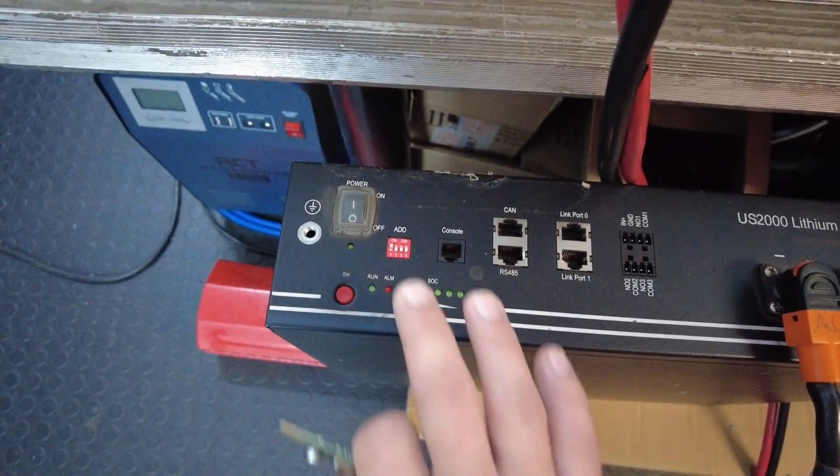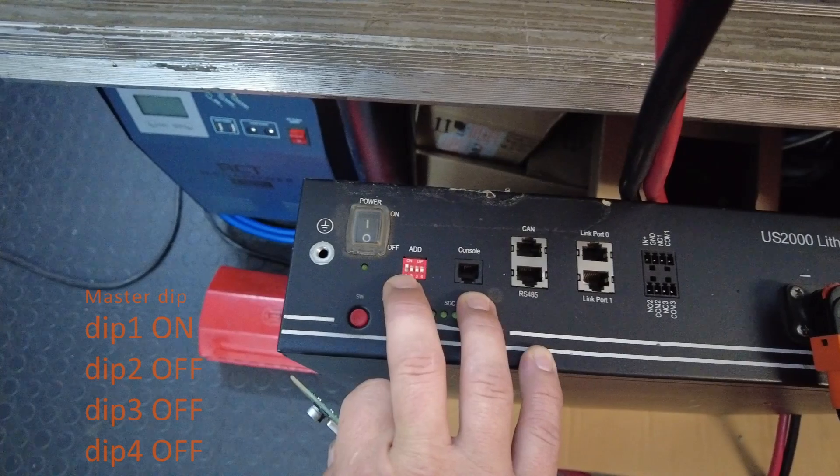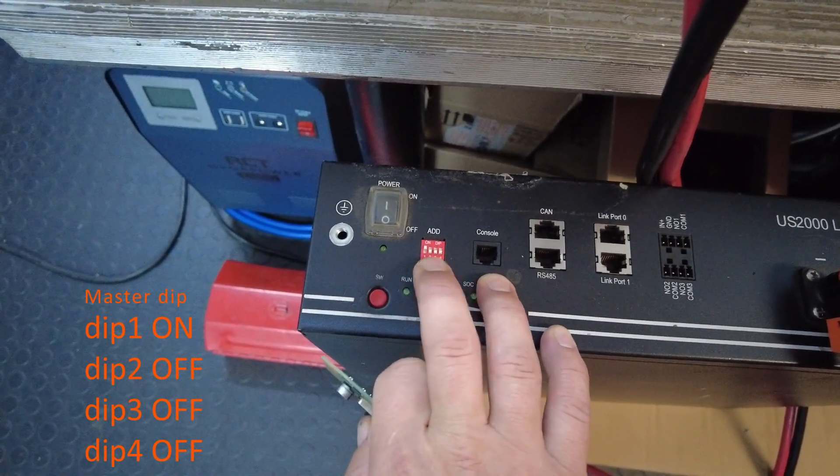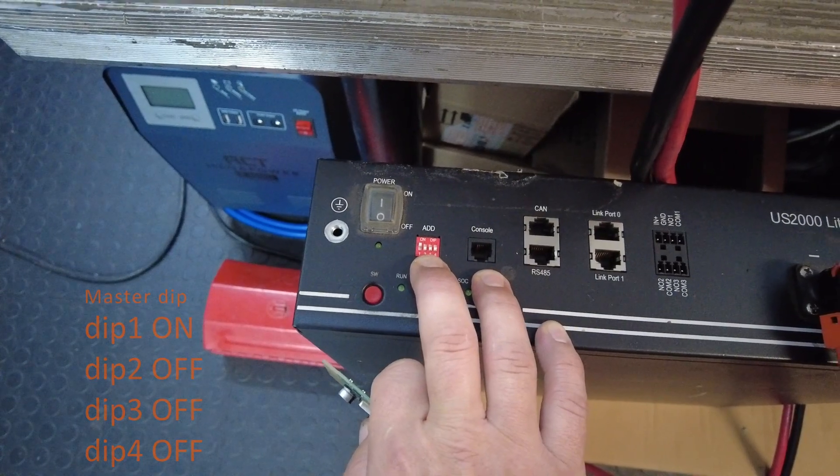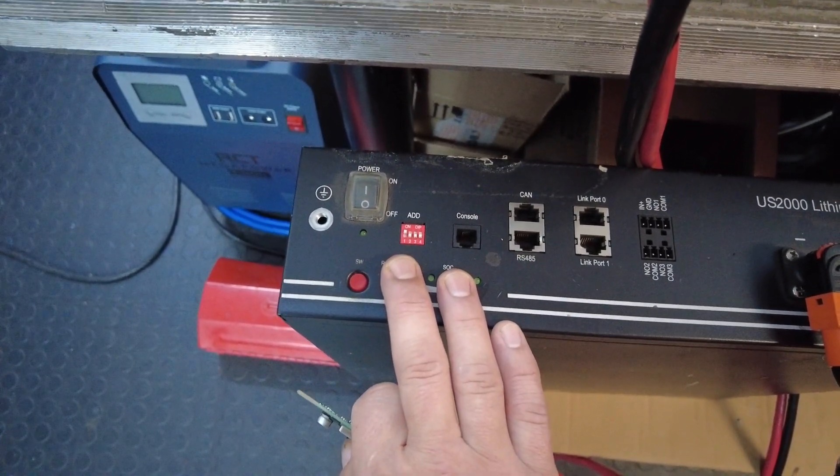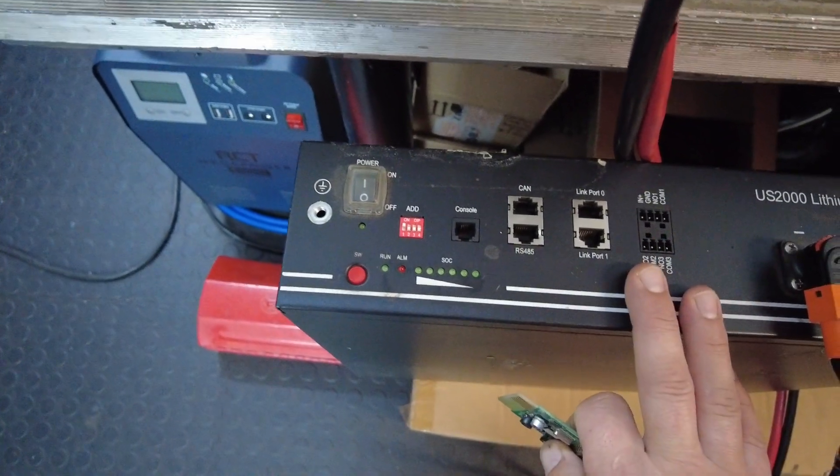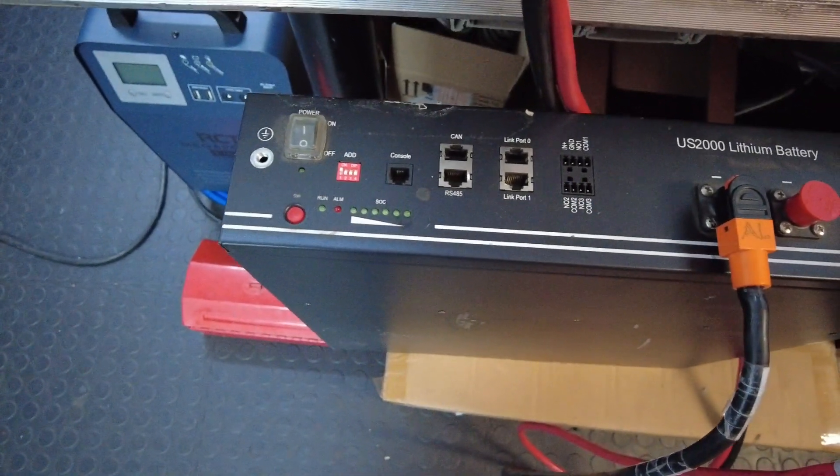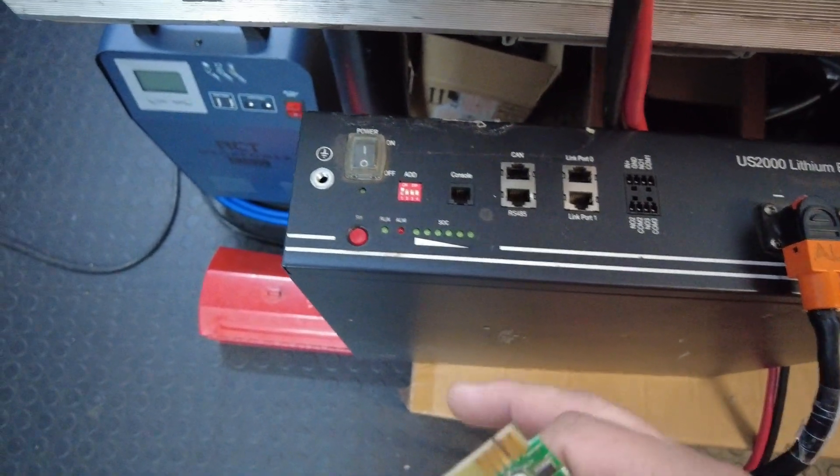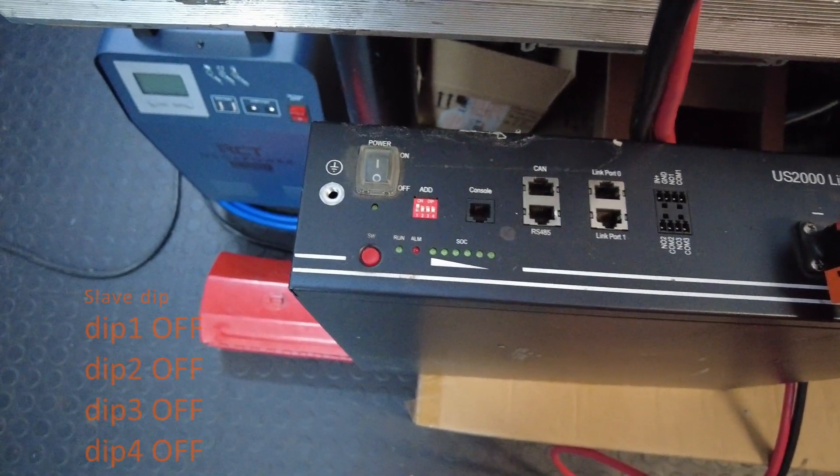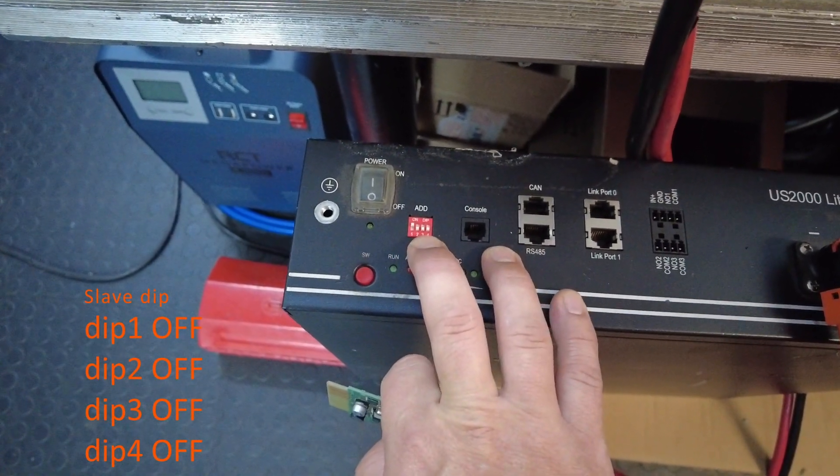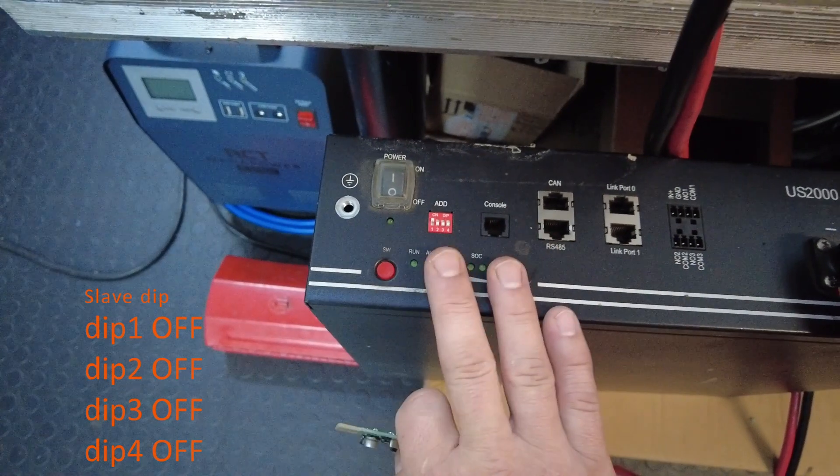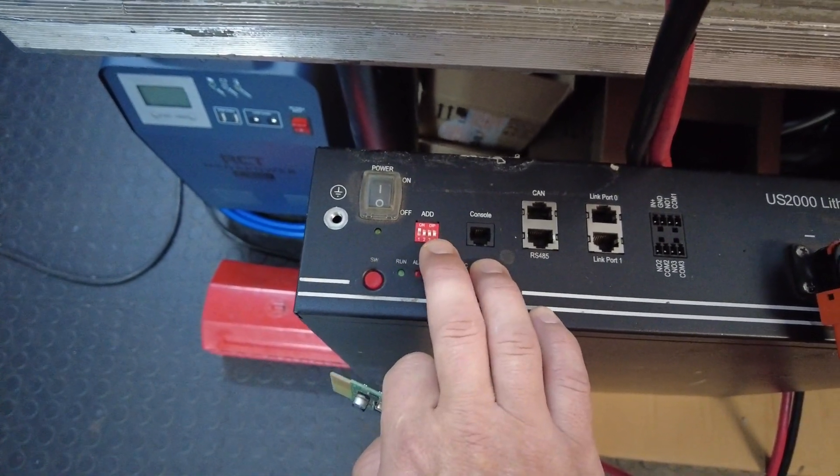For the dip on the battery, the very first dip needs to be in the on position. Dip number two, three and four will be in the off position. Note that this is your dip setting for the master battery. As soon as you add on multiple batteries, your slave batteries two, three, four and so forth, all dips need to be in the off position. It's only the master battery that's set to one, zero, zero, zero.